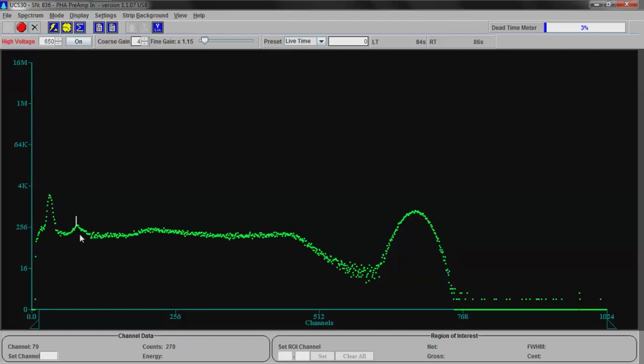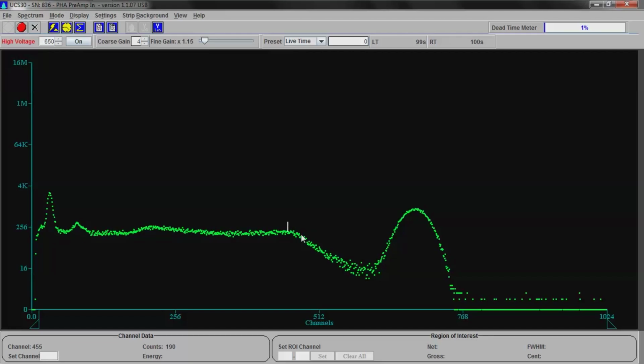Energy is hitting the lead, and I'm getting this back as a result. This is pretty much in all of my spectrums. I'm going to try to get rid of that with a little bit of tin and copper together as shielding. This right here is a backscatter peak, and this is a Compton edge. There are two interesting facets of the detector itself and the way photons interact with matter, which are beyond what I'm going to go through today, which is how to analyze this sample.